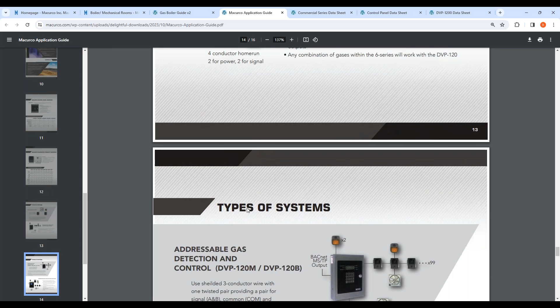When you get to the addressable systems, this is a big educational tool we train on with contractors - the term daisy chain and T-tapping coincide together. What you see here is a daisy chain, going from one to the next, to the next, to the next. If you were to take a T-tap, you're going to have a world of problems at our panel. Within the Modbus communication protocol, we are not capable of T-tapping, so we want to make sure that's upfront and transparent.